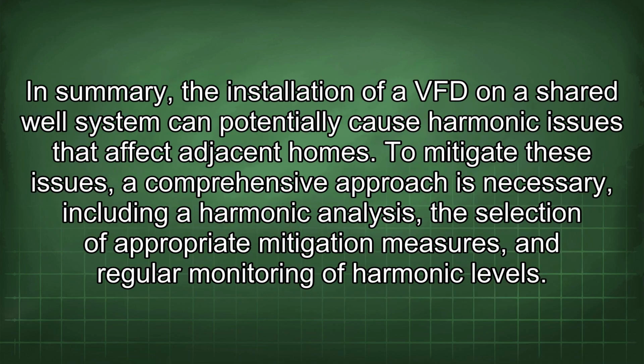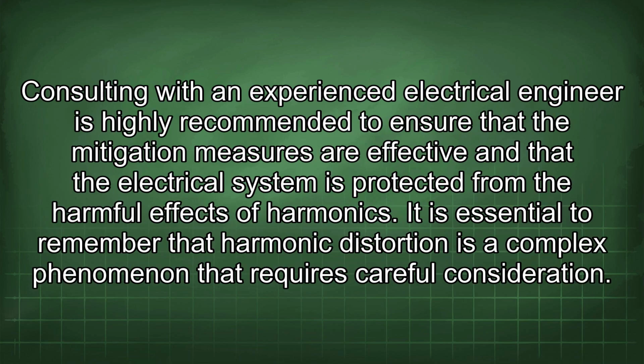In summary, the installation of a VFD on a shared well system can potentially cause harmonic issues that affect adjacent homes. To mitigate these issues, a comprehensive approach is necessary, including a harmonic analysis, the selection of appropriate mitigation measures, and regular monitoring of harmonic levels. Consulting with an experienced electrical engineer is highly recommended to ensure that the mitigation measures are effective and that the electrical system is protected from the harmful effects of harmonics.